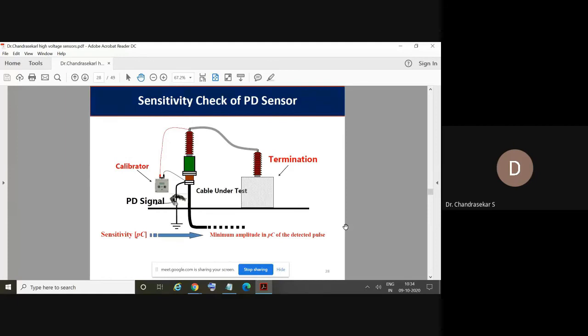Why I am telling this is that when I was a postdoctoral research fellow in Italy, we used to go for real-time monitoring systems in tie-up with industry. One day we went for underground cable monitoring. The practice is that the cable will be several kilometers long. Therefore, we need to monitor the cable properties, particularly the PD activities, at different terminations and junctions. So we need to start the procedure early in the morning, so that before 7 or 8 o'clock in the evening we can finish the entire work.